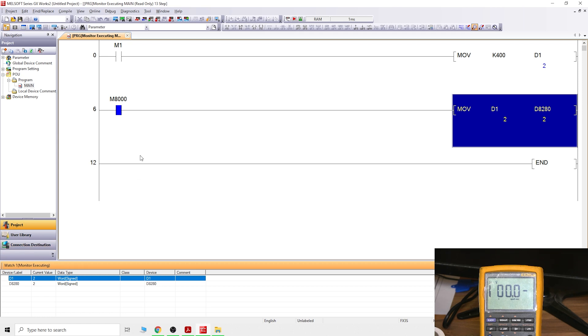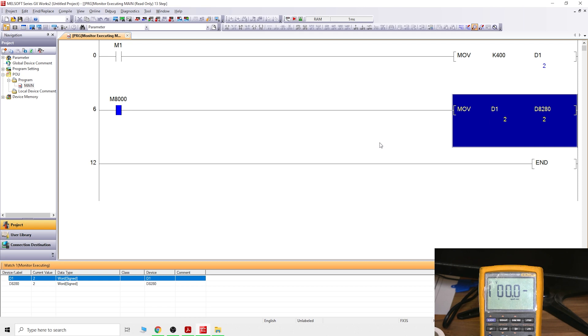So here we go. This is it, ladies and gentlemen. This is how you get your analog output card going, and this is pretty much what the values are represented. This is how 10 volts are represented. Zero to 10 volts will be from zero to 4,000 digital numbers, so you can do whatever you wish, however you want to control it, whatever the system you're going to control. We definitely later on, in the future, we're doing a little bit of process signal processing for drives.